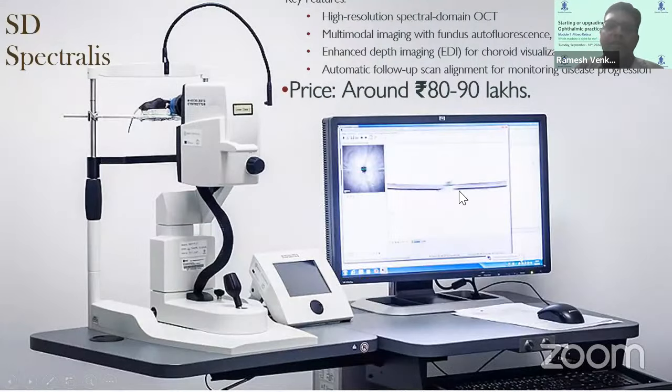Now, let's talk about the Spectralis or the Heidelberg, which is one of the high-end OCT machines in our center. You use it for color fundus photography and pseudo-color imaging, and in addition, you use the OCT and the OCT angiography module. It also gives enhanced depth imaging to visualize the choroid, and a lot of automated measurements in the form of an area measurement tool, and calipers which measure the height of the macular thickness. The price for this machine is around 80 to 90 lakhs, and it is one of the most frequently purchased machines, produced in Germany.